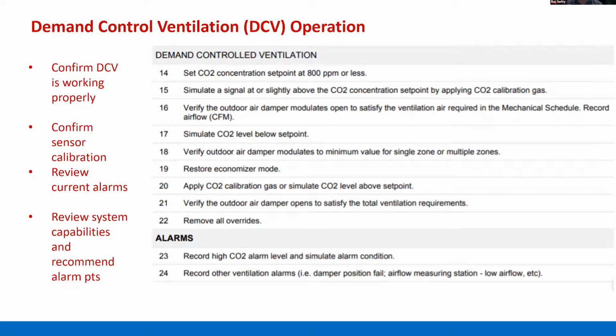is going to adjust some of the disabling of the demand control ventilation when there is a block load type scenario. So if you have a classroom corridor and a gym, if you disable it, then the gym might suck in all the fresh air. So the new guidance is going to have you look at the way the DOASs were designed and make sure that you might have a higher set point on, let's say, a gym. If the gym is not going to be used and it's on the same DOAS, then that one might go to a higher CO2. So as you start to look at your design scenarios, 800 and disabling it is the starting point, unless it's on a block load scenario.